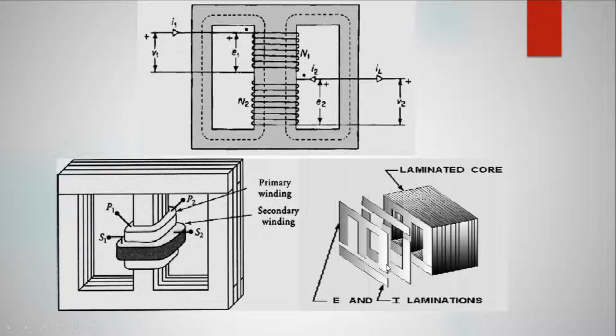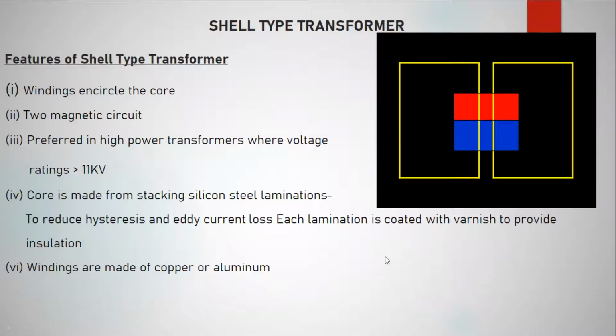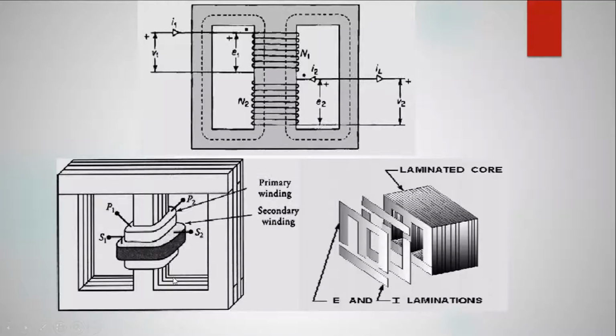So each lamination is insulated from each other. While it has been staggered and compressed together to form this much thickness of core, the laminations are insulated from each other, to reduce hysteresis or eddy current loss. Windings are made from copper or aluminium. Once again the same thing here: the windings are made from aluminium or copper.